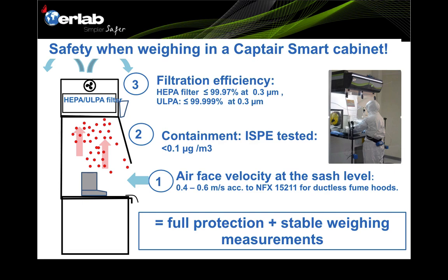This slide shows how the Captair Smart filtered fume hood provides full protection and a stable weighing environment. At the sash opening, the face velocity is maintained within 0.4 to 0.6 meters per second according to NFX 15211 standards, and it also complies with local DOSH requirements for fume hoods. Having passed the ISPE containment test with results below 0.1 micrograms per cubic meter, the Captair Smart is suitable for OEB 3, 4, 5, and 6 applications. Filtration options include both HEPA and ULPA filters.